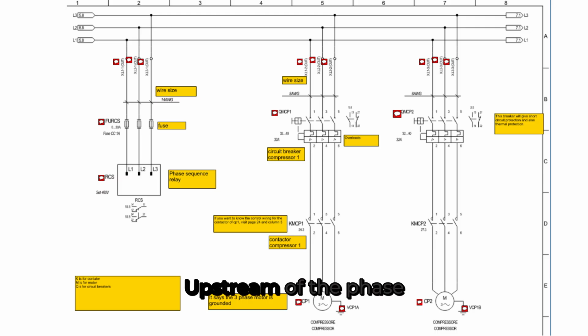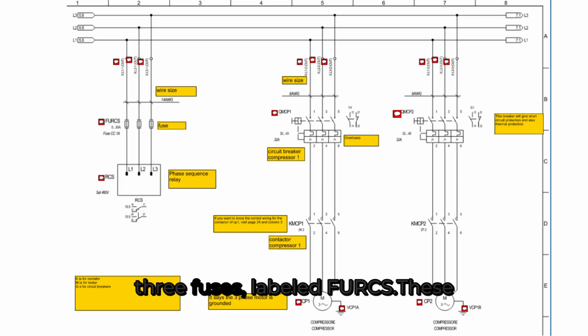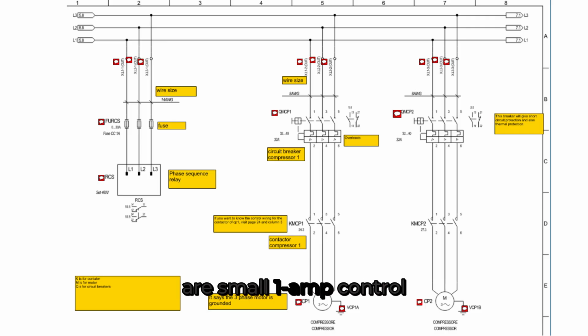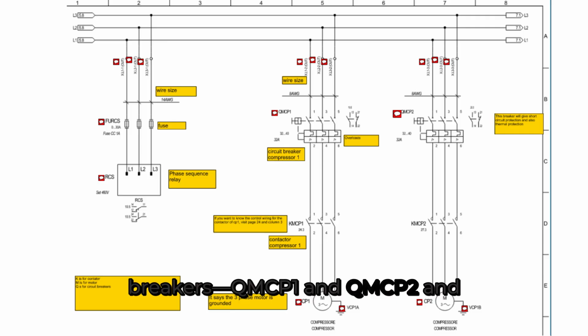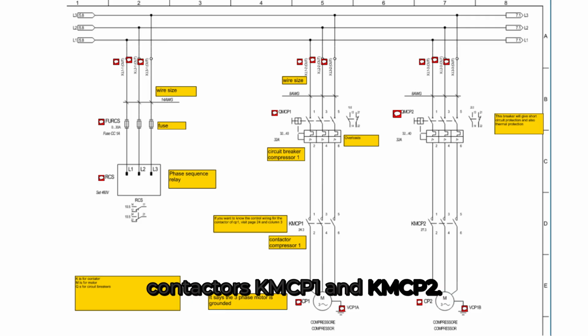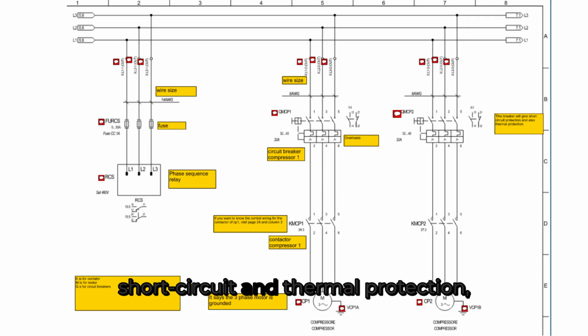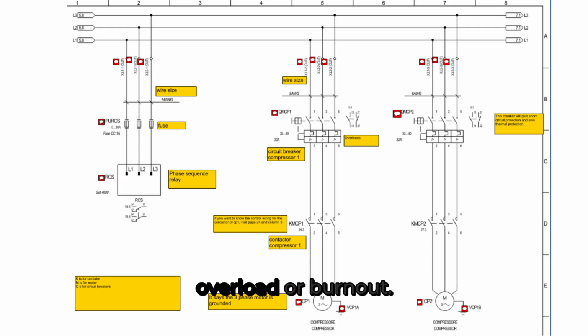unit. Upstream of the phase sequence relay, we have three fuses, labeled FURCS. These are small 1 amp control fuses rated for Class CC1A. 14 AWG wire is used for the phase monitor. Next, the power lines feed into two identical compressors, CP1 and CP2, where 1 represents refrigerant circuit 1 and 2 represents circuit 2. Upstream of the compressor motor, the unit has two identical sets of circuit breakers, QMCP1 and QMCP2, and contactors, KMCP1 and KMCP2. These circuit breakers are rated at 32 amps, and they provide both short circuit and thermal protection, preventing the compressor from overload or burnout.